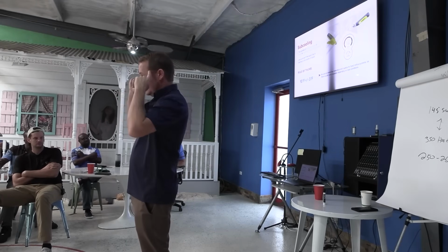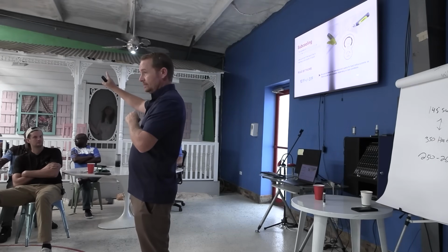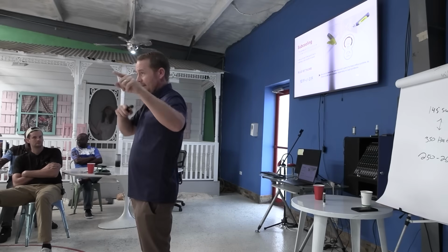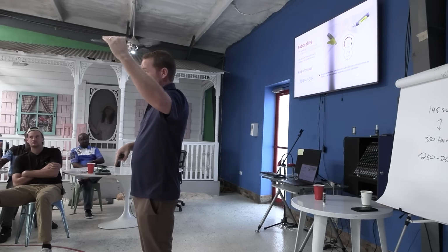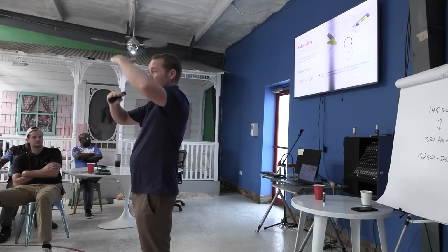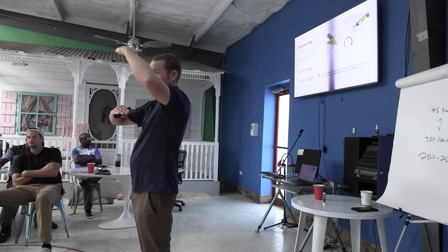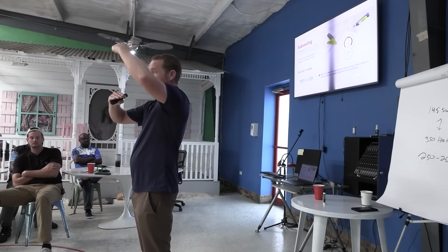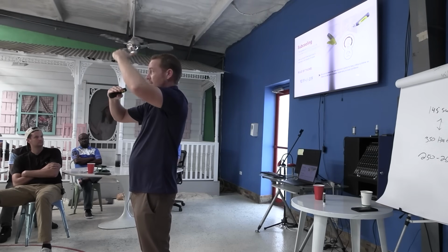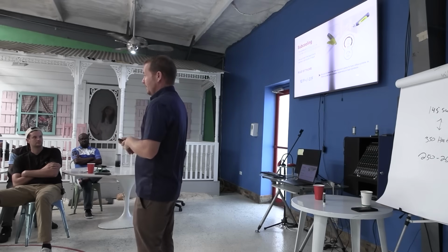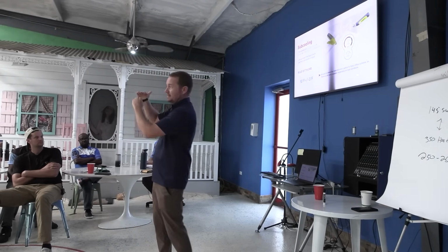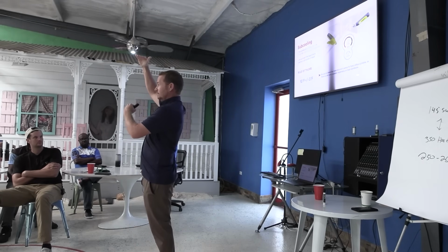Suction pressure is evaporator temperature. Liquid pressure is condensing temperature. Subcooling is how much liquid we're stacking in the bottom of the condenser. Higher subcooling means we're stacking more liquid. Lower subcooling means we're stacking less liquid. In the evaporator coil, higher superheat means our coil's not as full. Lower superheat means our coil is more full.